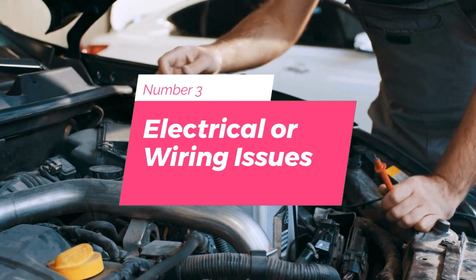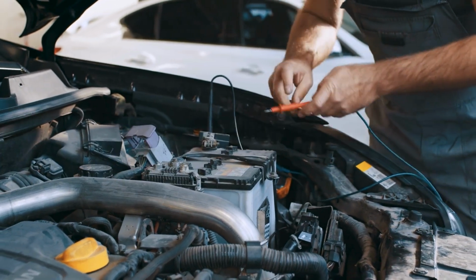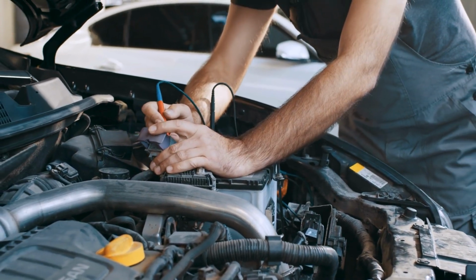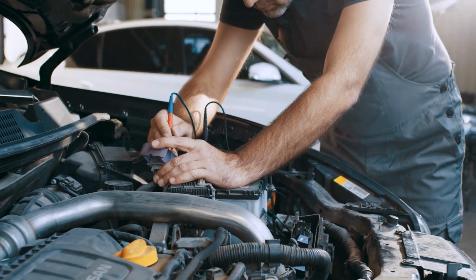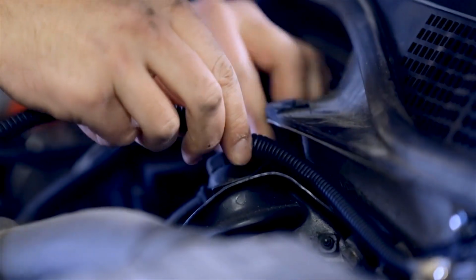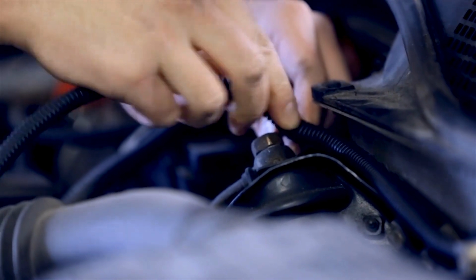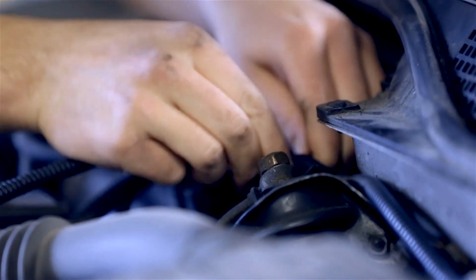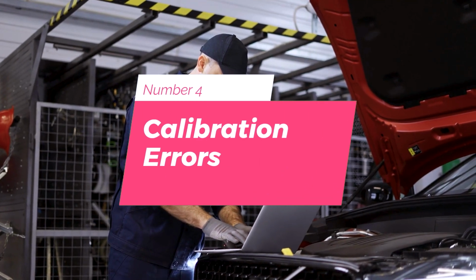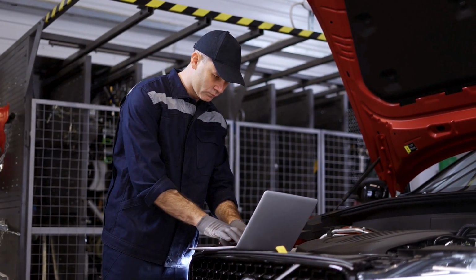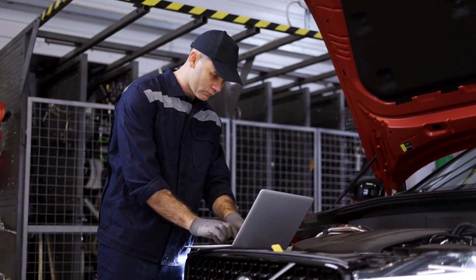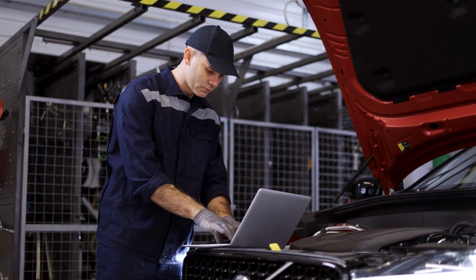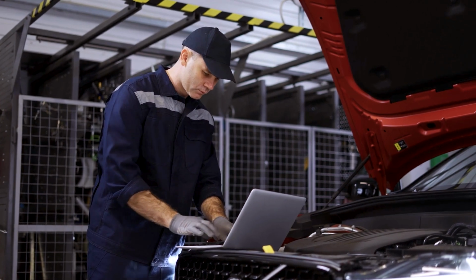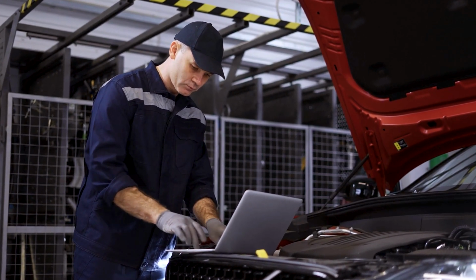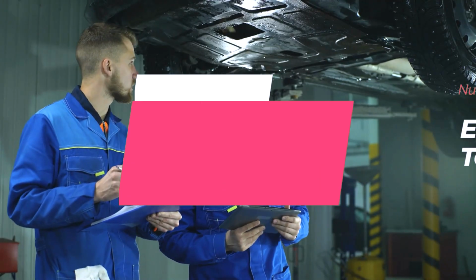Number 3. Electrical or wiring issues. Problems with the electrical connections, wiring, or the sensor's connectors can cause issues with torque sensor readings. Loose connections, damaged wires, or faulty connectors can also disrupt the sensor's performance. Number 4. Calibration errors. Torque sensors need to be calibrated properly to provide accurate measurements. If the sensor is not calibrated correctly or if the calibration drifts over time, it can result in inaccurate torque readings. Number 5. Excessive torque load.